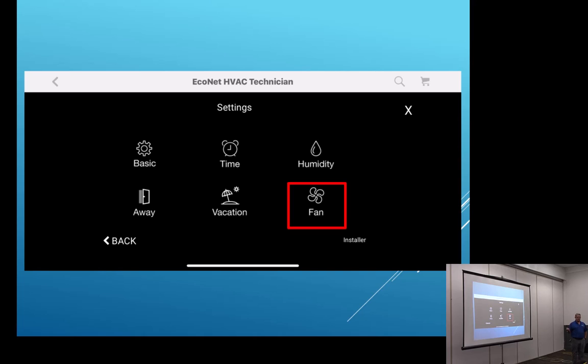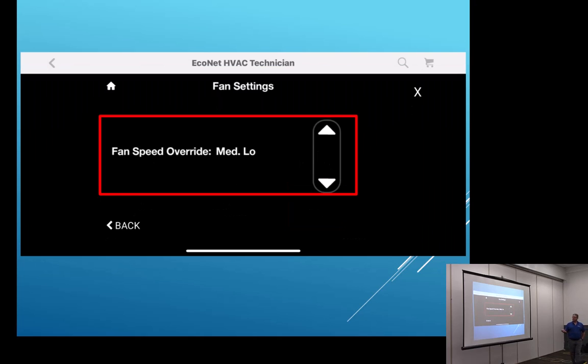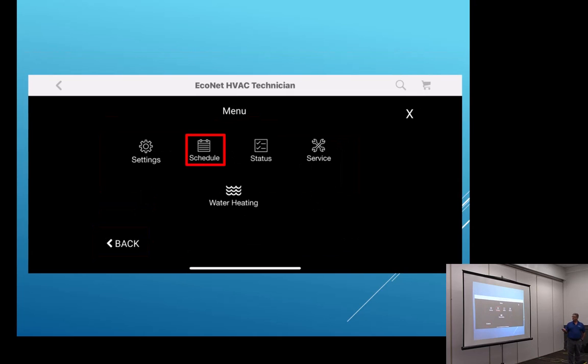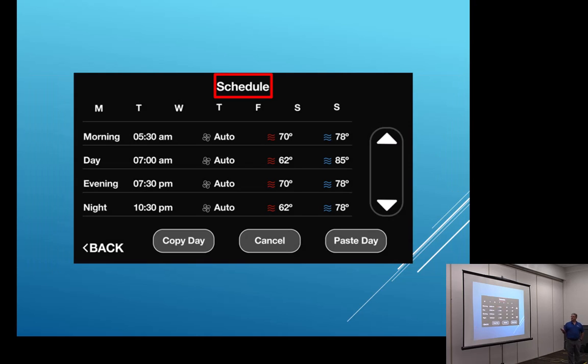This is that other place for that fan setting that I told you about. So if that homeowner changed it here and not at that other place that I told you about, this is where you've got to come and change it back. Okay? I wish they had just one spot for the fan, but they don't. So this is where we come in here and we can set it to medium, low, or whatever, and to auto. This is where we've got to change that fan setting.